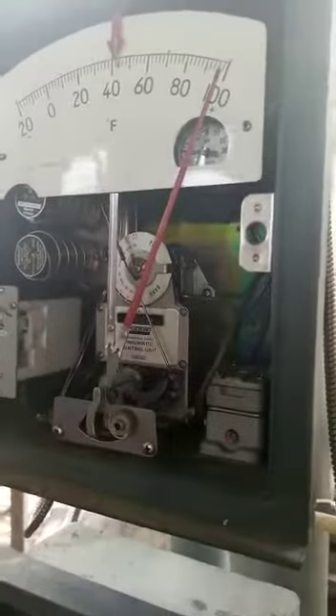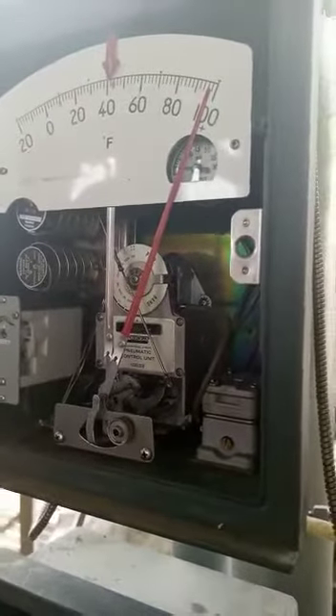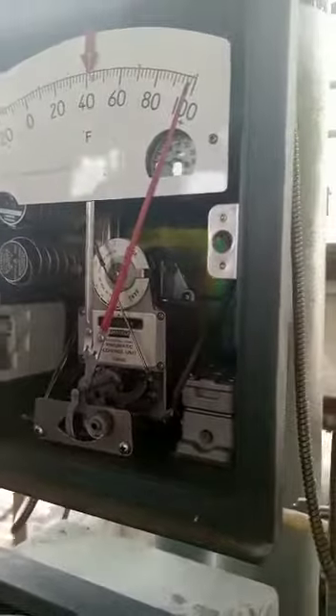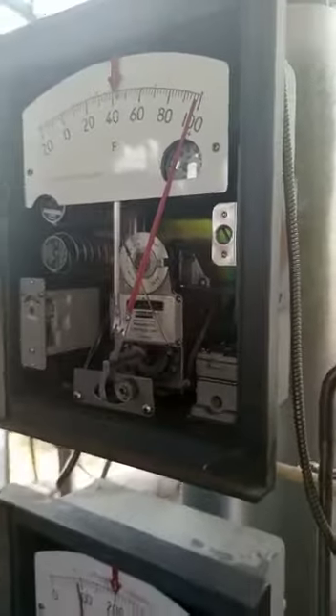You can see it's heating up, going close to 100. This is the manual pneumatic relay for this temperature controller. As you can see, this is the range of this temperature controller, minus 20 to 100 degrees Fahrenheit, Foxboro, and this is the adjustment for maximum and minimum. This place is for sensitivity.